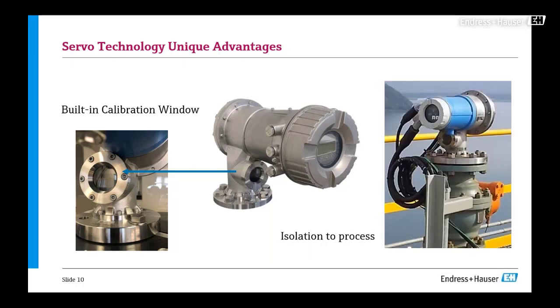Another one is what we call isolation from the process. If you refer, for example, to a BS standard, it also mentions that your gauge should be able to isolate during operation, maybe for maintenance. One of the good things about the servo gauge is you can hoist up your displacer, and then you can isolate by closing the isolation valve. And then of course, you still have your secondary gauge. If the primary is having an issue, then you can remove or isolate your gauge for check or maintenance work. So those are the unique advantages that you can get out of the servo technology.